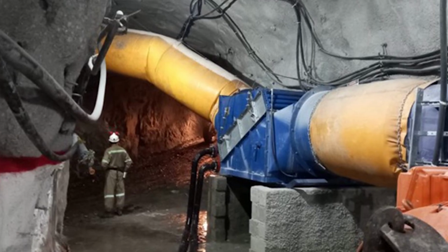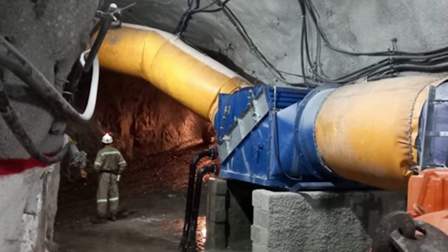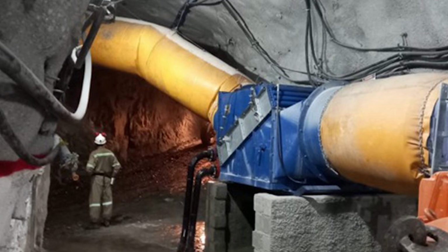Two methods distribute this cooling. Bulk air coolers function like massive radiators placed in the main airways. Ventilation air is forced through these units, dropping its temperature before continuing to the working areas. But the more efficient method involves slurry ice, a mixture of chilled water and ice crystals that can be pumped through the existing water lines.